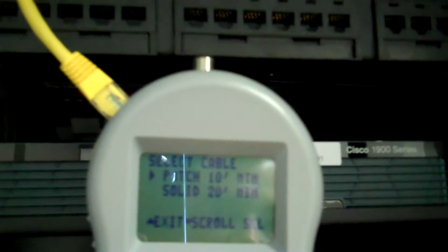So I hit the down arrow for test. It asks me whether I'm testing a patch cord, a minimum of 10 feet, or a solid copper cable, a minimum of 20 feet. I want solid, 20 feet. Select. Okay, now it's running the test.